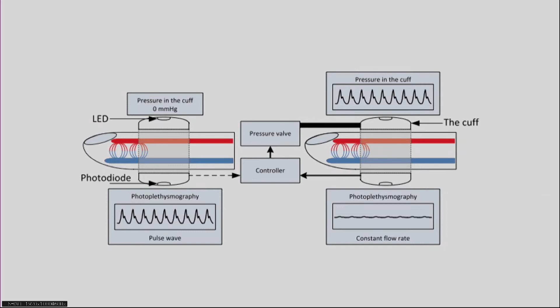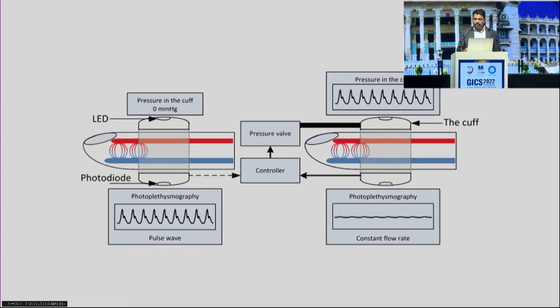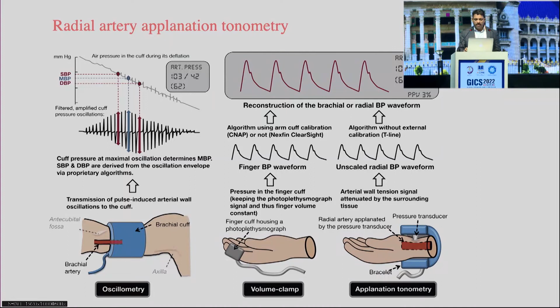But if you use a cuff pressure which is close to the pressure in that artery, and you want to have a similar blood flow, the blood flow remains constant, but the pulsatility goes out. And this pressure, which is required to take out the pulsatility of the blood, is reflected at the top as a non-invasive arterial tracing. So once the pulsatility goes out, that is reflected as an arterial tracing, and from here they calculate the cardiac output. And again, the correlation remained a challenge.